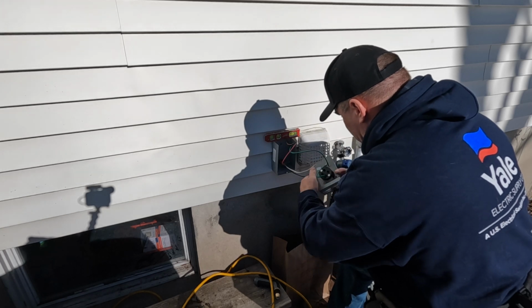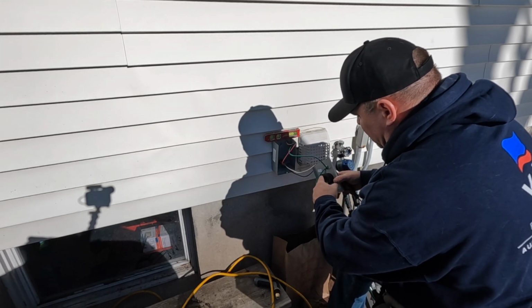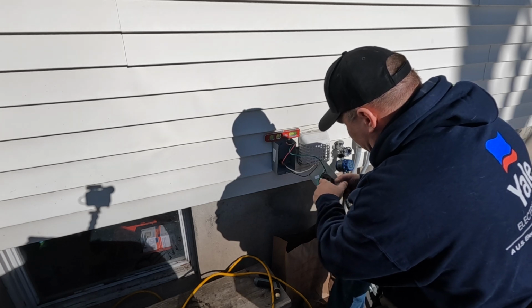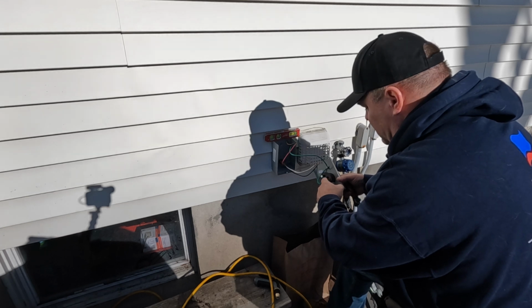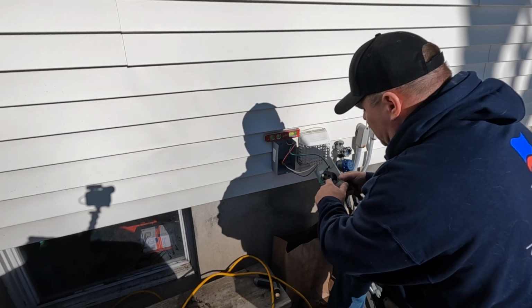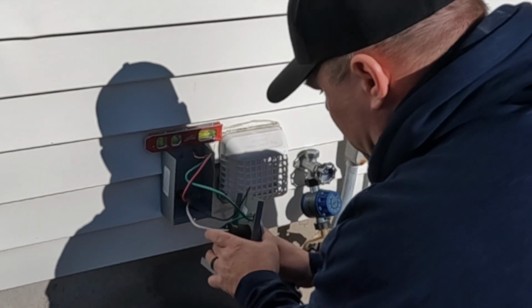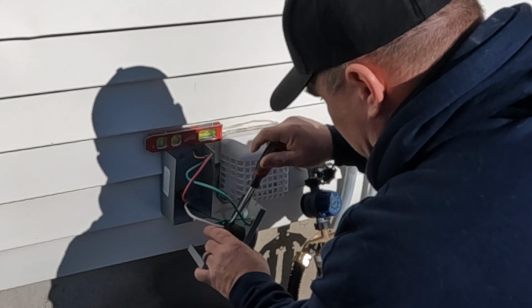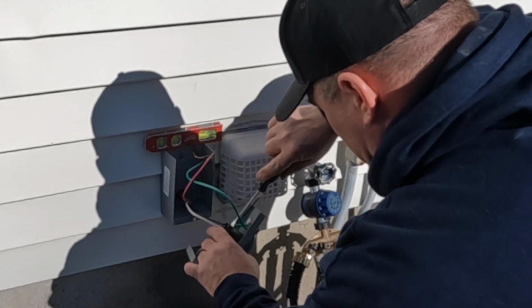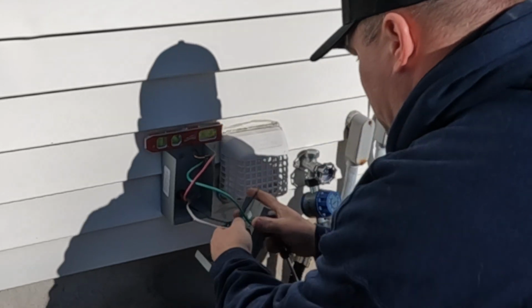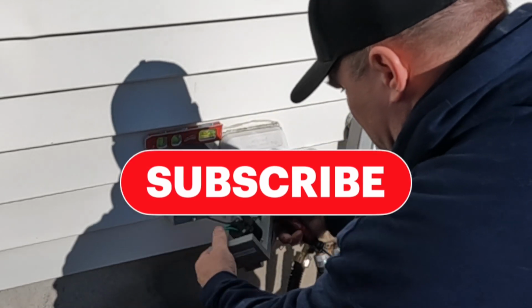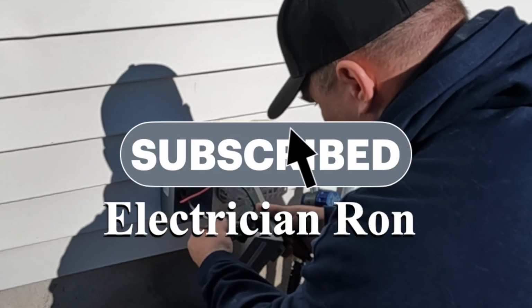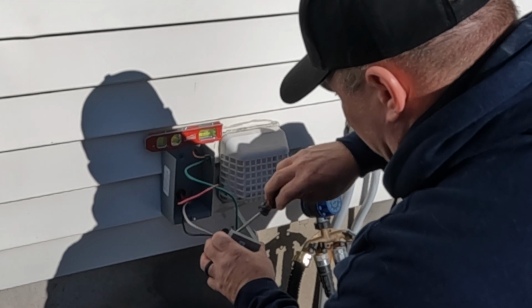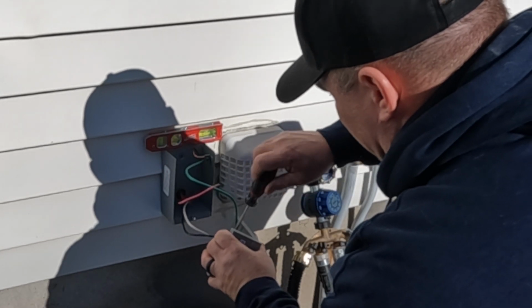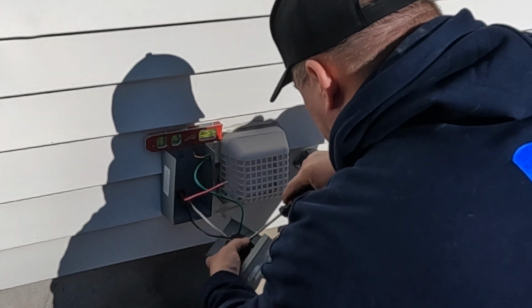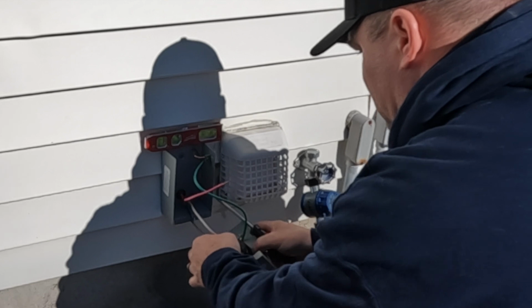All right, so the white is open, and the white's always going to be opposite of the ground. All right, marked W. Then X and Y are always going to be your ungrounded conductors, your 240 volts, 120 here and 120 here, ground and neutral. Okay, that's in there good. Do black over here. The terminals come open, you just got to tighten them down. I usually just tighten them down by hand. Make sure it's good and tight, not over tight, just snug so it doesn't come out.